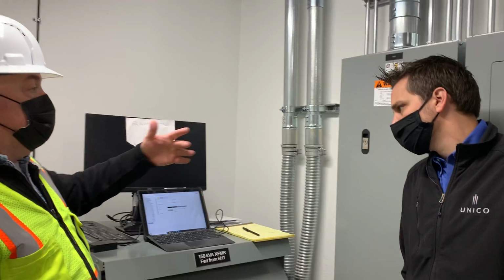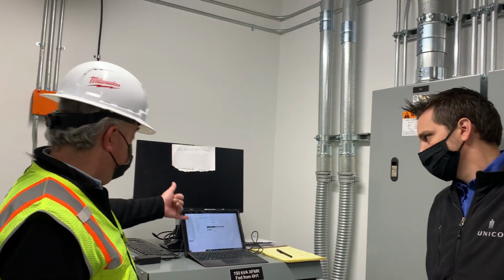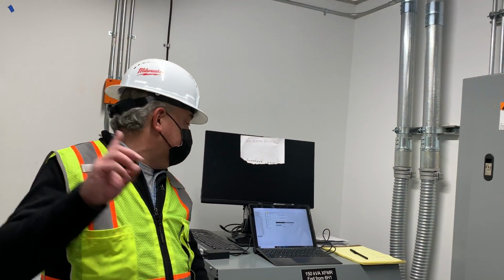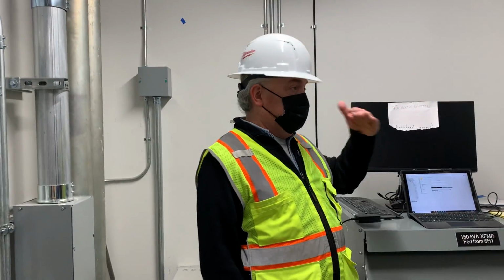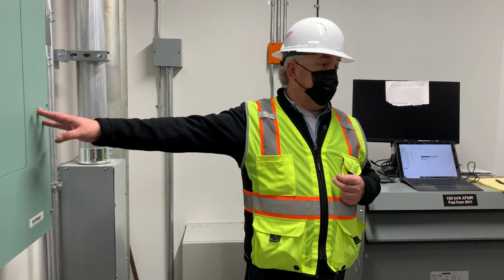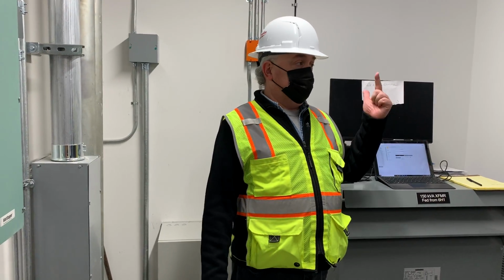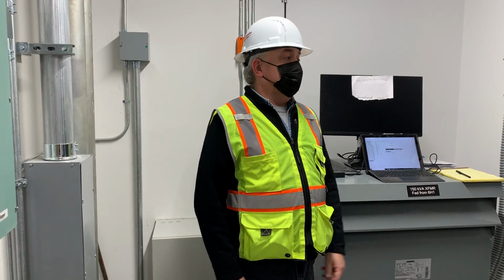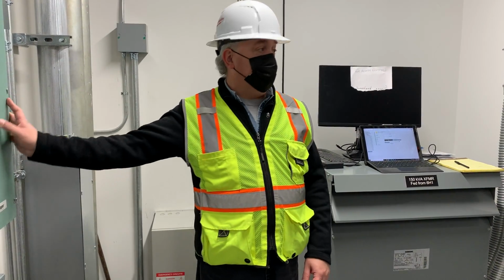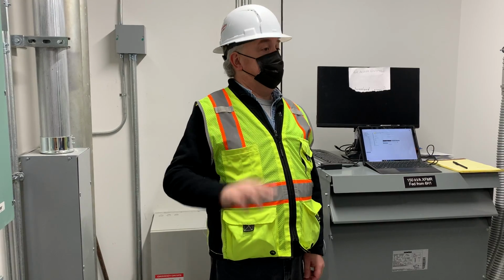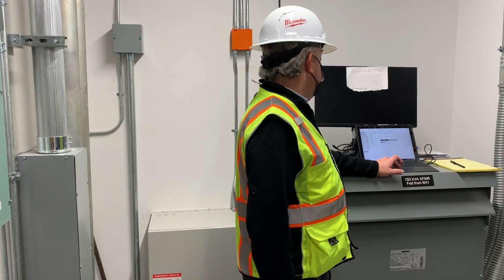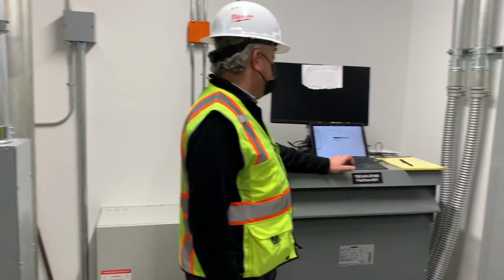So our general lighting on levels 5, 6, and 7, L5, L6, L7. We're currently looking at the 7th floor panel, which only has the L7 general lighting and the chandelier. There's only 2 relays in use up there. In here, we're just using 4, L5, L6, exterior, and signage. And how many relays are in there? 24 per floor. Or excuse me, 24 in this panel, 24 in this panel. There are only the 2 panels. There's not a dedicated panel for 5. It's shared out of 6. Yeah, from here I can turn individual loads on and off.